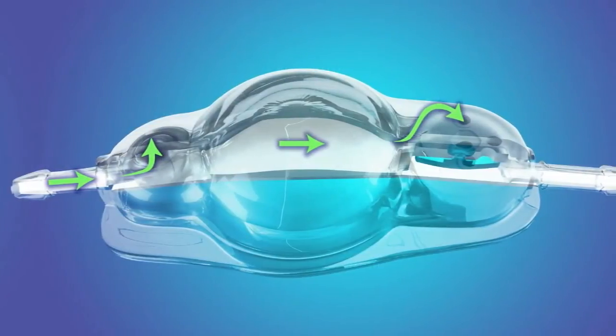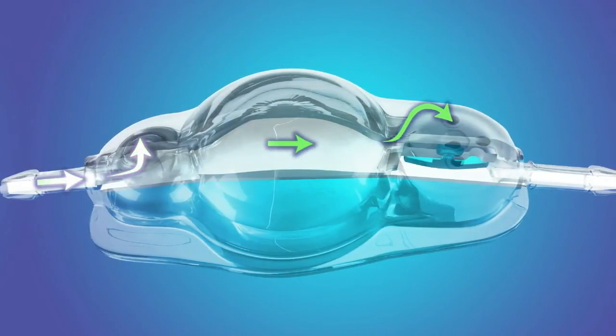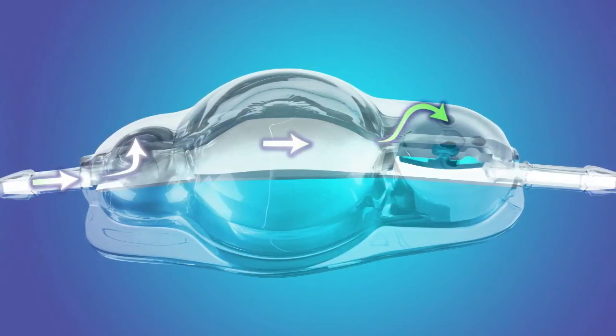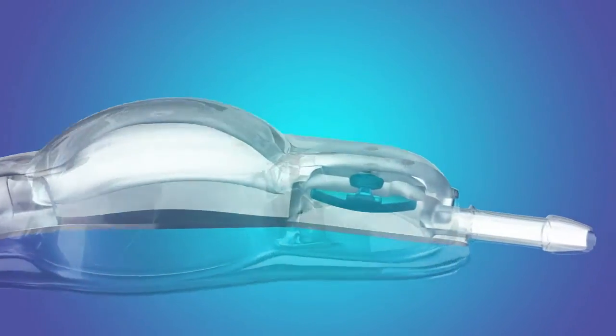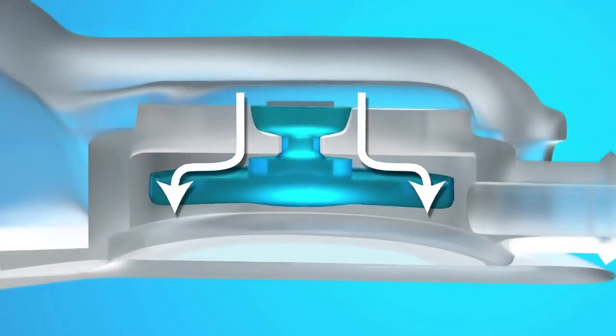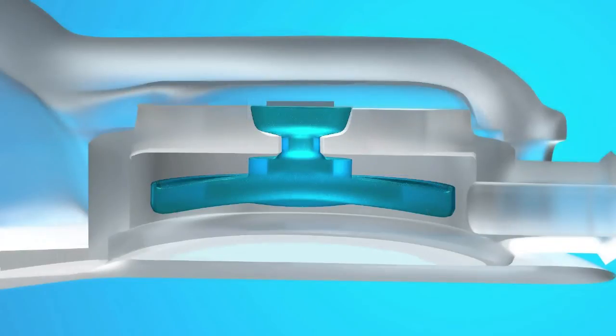As CSF flows through the contoured valve, it enters the inlet connector, flows by the proximal occluder, and into the central reservoir. For sampling CSF, the reservoir dome can be accessed using a 25-gauge or smaller non-coring needle. From the reservoir, CSF flows through the valve mechanism flow holes. The inlet CSF fluid pressure causes the umbrella-shaped membrane to open when intracranial pressure, ICP, exceeds the resistance of the valve umbrella or membrane. When the ICP is lower than the resistance of the silicone umbrella, the mechanism closes.